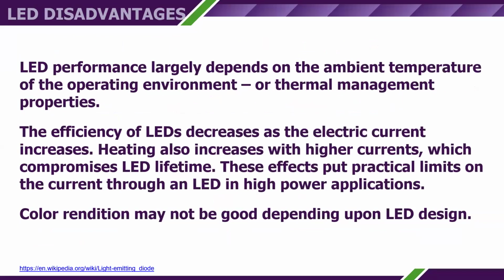The LED disadvantages: performance largely depends on ambient temperature. LEDs are very heat sensitive, but with the proper design and heat sinks installed, they work quite well for airfield lighting fixtures. And the efficiency of LEDs decreases as electric current increases. If you increase electric current, that increases heat, so that's also an issue. But again, the designs today are pretty good designs, and they seem to last for quite a while.